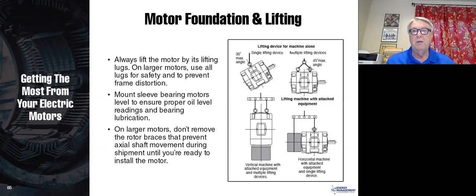that. Let me just point out that when you lift the motor, you want to lift it by the lifting rings, and if a motor has 2 lifting rings, make sure that you use both of them, and you have a maximum of a 45-degree angle here. Here's a vertical machine. Try not to let it tilt, lift it vertically, and use both lifting eyes.